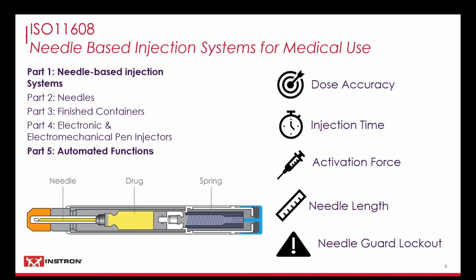Depending on the device type, as mentioned in the last slide, the scope of this test method can change. For example, variable dose multi-use devices require the most stringent testing, ensuring that a minimum, average, and maximum dosage can achieve the required accuracy, and the last dosage error is below a certain threshold.